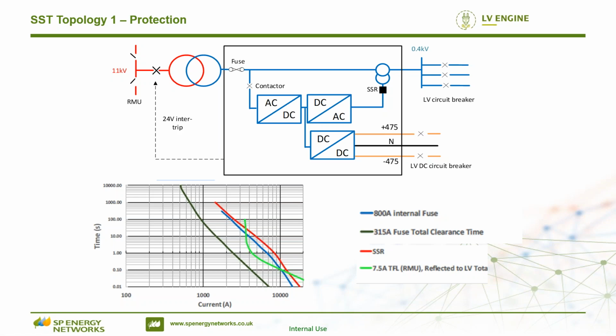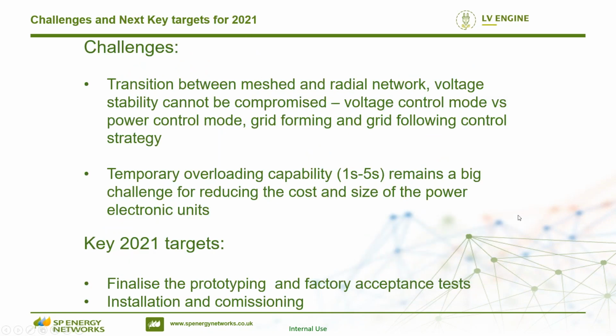So there's an element here which is a very important part of this protection scenario, which is the solid state relay, which can bypass our coupling transformers when it sees high current going through. That can also be used as an operational scenario when you want to bypass the whole power electronic. So you see the solid state relay should be somewhere here. The fault level withstand, or the thermal capability, of that should be above the fuse we have at this point, which is an 800 amp fuse.